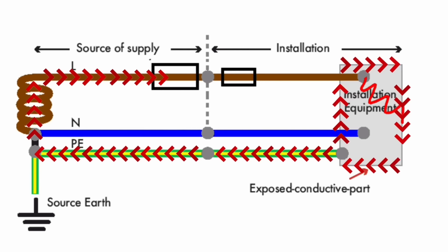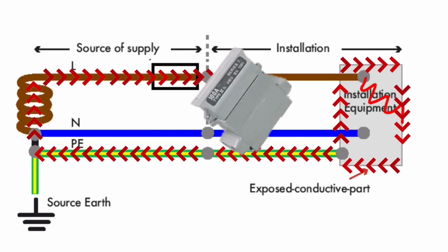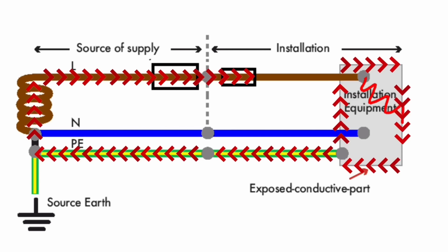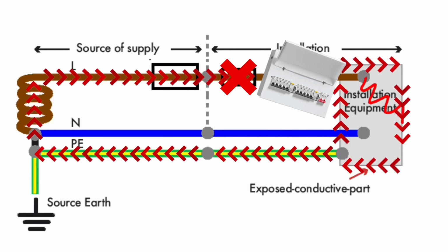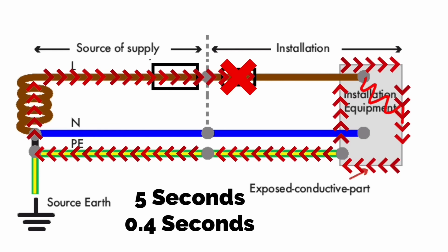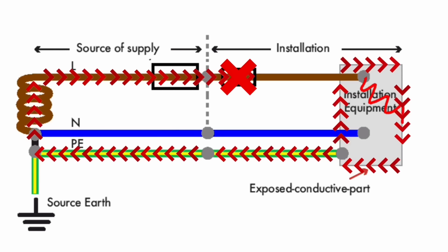the circuit. The fault current will pass through the main cutout fuse rated at either 100, 80 or 60 amps, but will not cause operation. The fuse that will operate is the one closest to the fault. In this case, the fuse located within the consumer's unit will operate, clearing the fault in circuit. This is the full earth fault loop path and needs to be a very low impedance in order to generate a very high fault current to cause rapid operation of the overcurrent protection device. We looked at 2 maximum times for disconnection, either a maximum time of 5 seconds or a maximum time of 0.4. I have described to you the earth fault loop path for an installation connected to a TNS earthing arrangement.